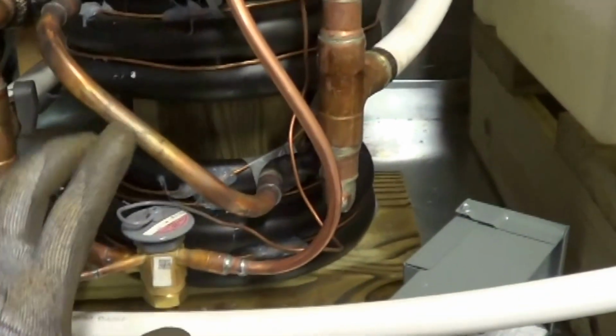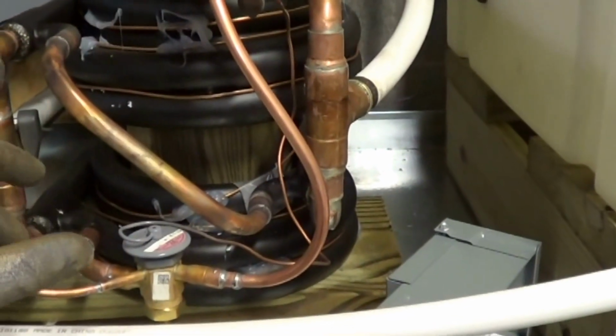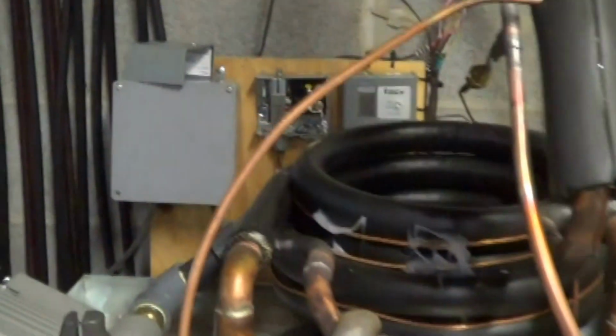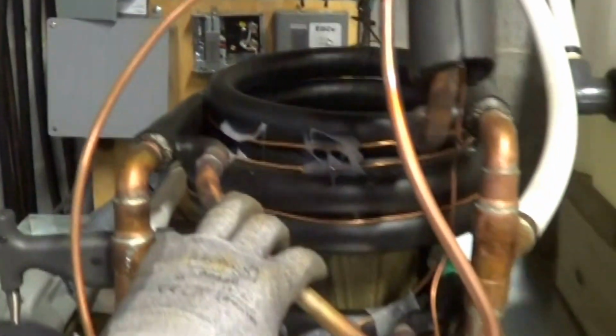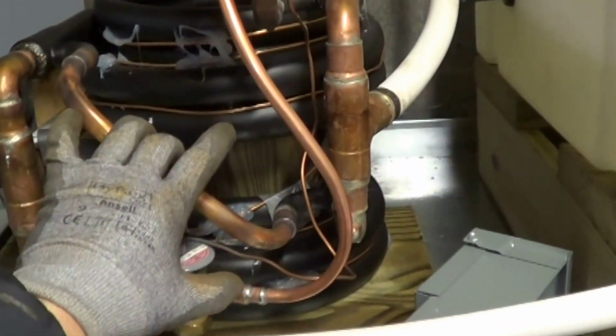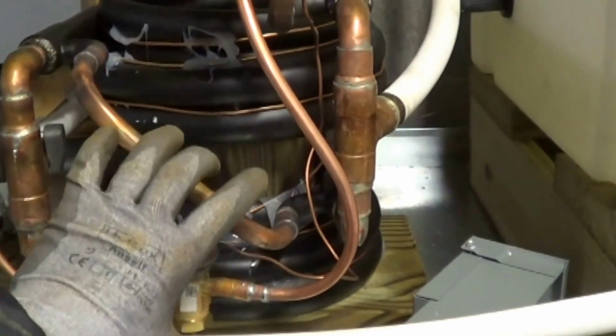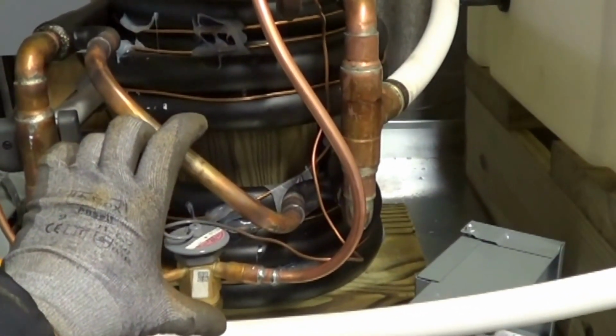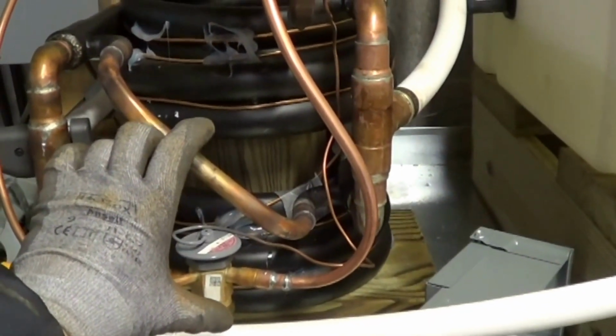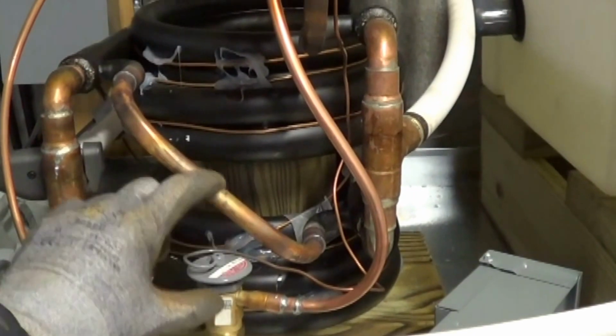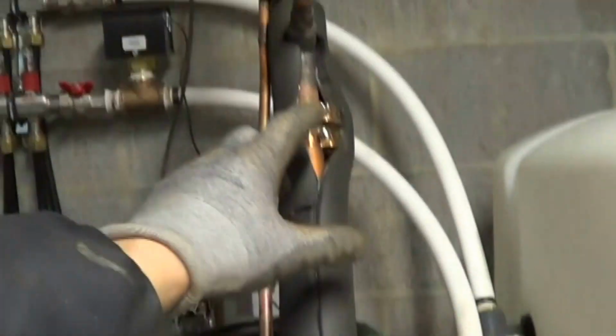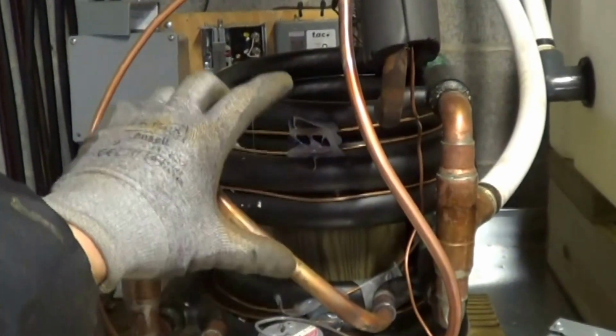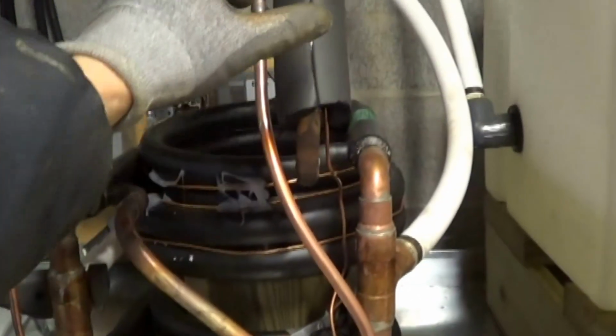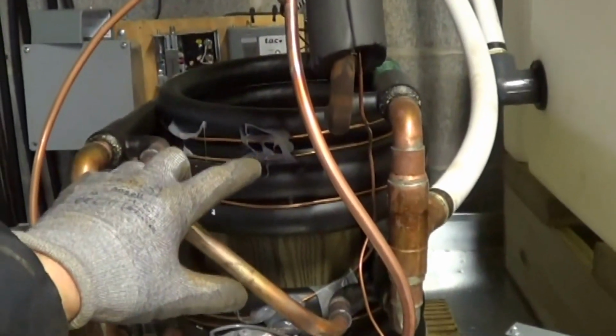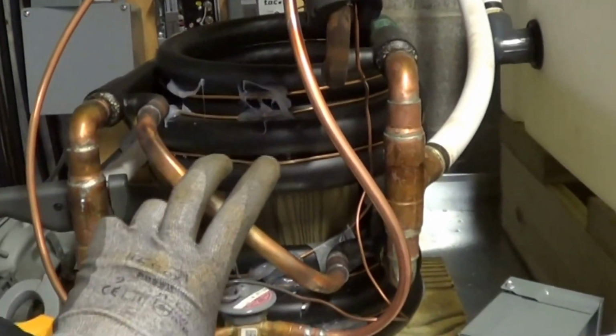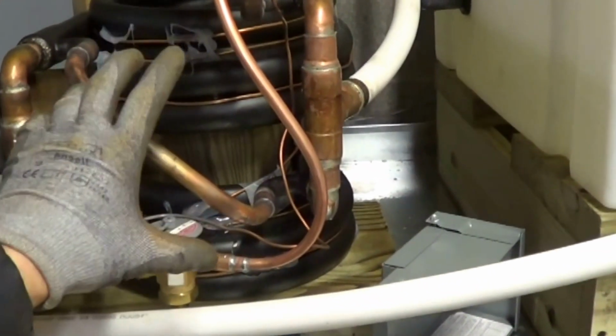But the head pressure runs up on a defrost, and I actually ended up hitting the 500-pound pressure shutdown. Because what happens is that this thing is already over half full of liquid, and then when it switches to cooling, the expansion valve feeds more because the bulb is hot, and it ends up going 100% full of liquid. And then the expansion valve starts pinching back, but it only pinches back to 3/4 full of liquid. So we end up with too much liquid.